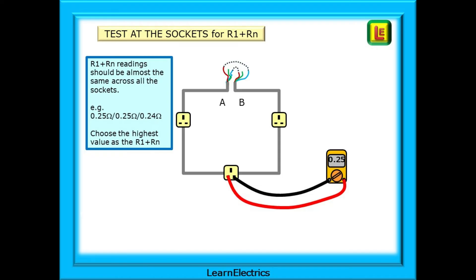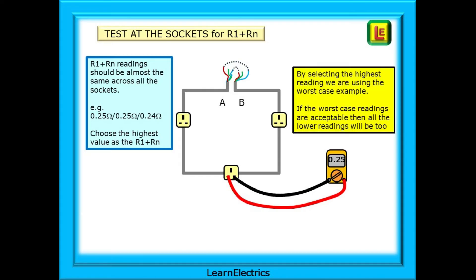And we choose the highest value as the big R1 plus Rn value. By selecting the highest reading, we are using the worst-case example. If the worst-case readings are acceptable, then all the lower-value readings will be acceptable too.